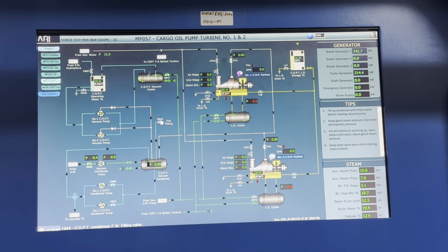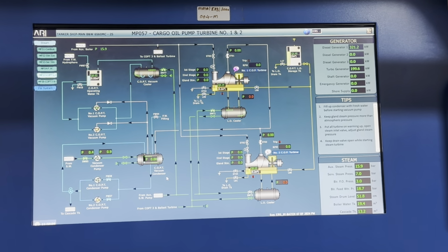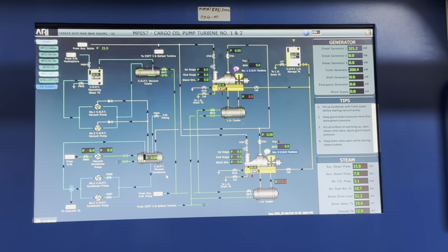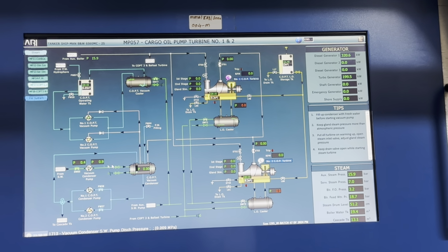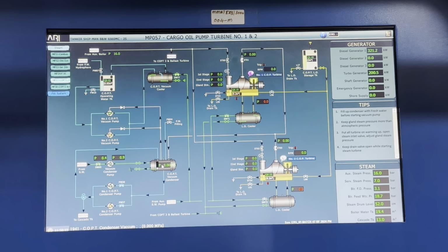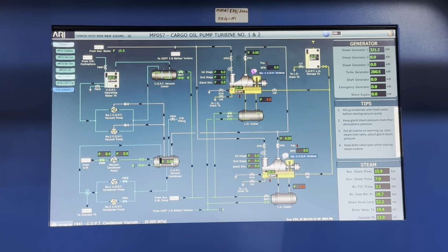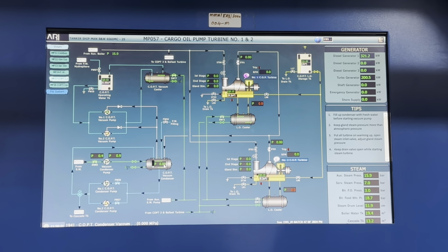So now you can close this water. The water is there, this is enough. Now you see whether the vacuum is building up or not. Otherwise there is some mistake. Where is the vacuum gauge for this? This one's pressure. Yes, there is a vacuum gauge. Okay, so it is not making any vacuum. Maybe the steam is not coming so far.